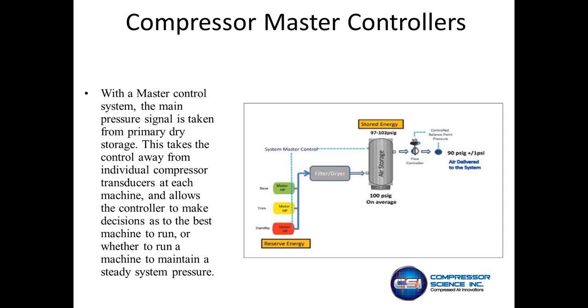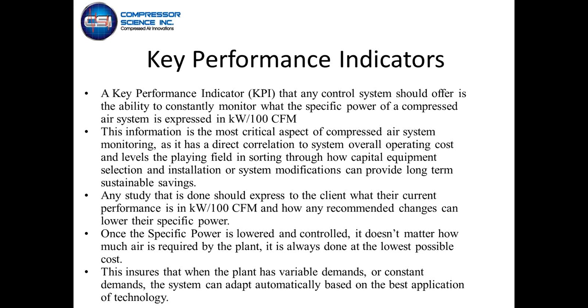Compressor controllers are, again, a great opportunity for energy savings because we're now taking the control away from individual transducers on each compressor, and we're taking it over to one central transducer in the storage tank, and then the master controller tells which compressor, whether it's inlet valve modulation, whether it's load, no load, or whether it's VFD, it's deciding which is the most efficient way to run to maintain a steady pressure.